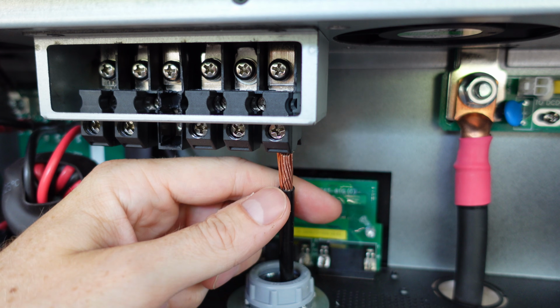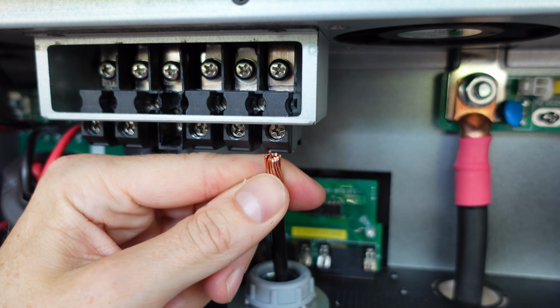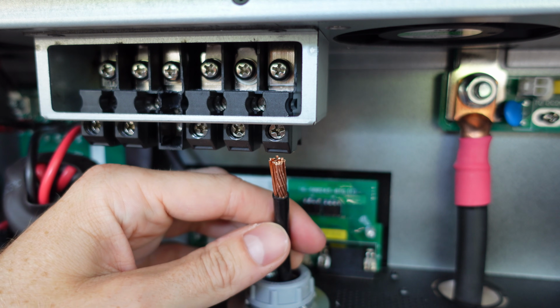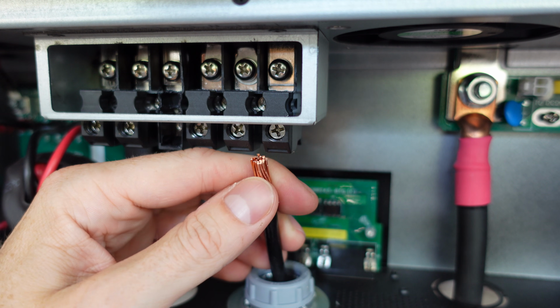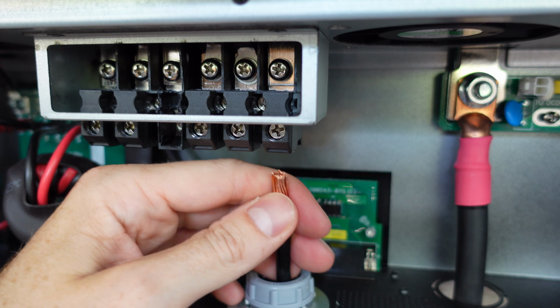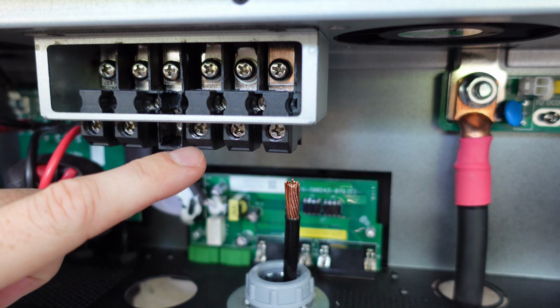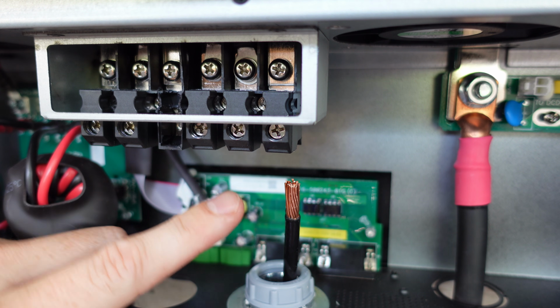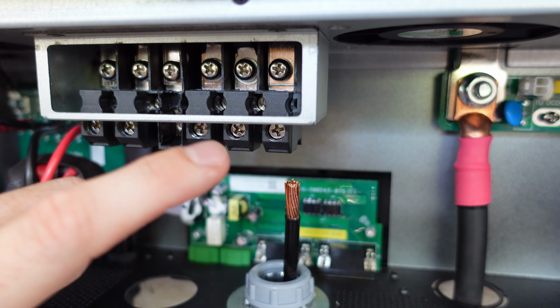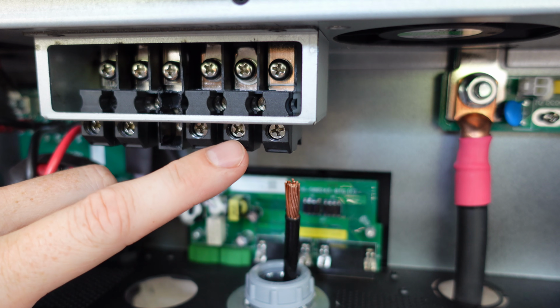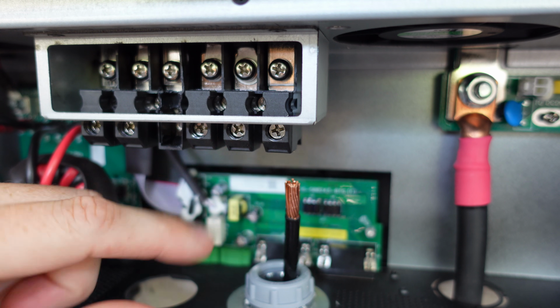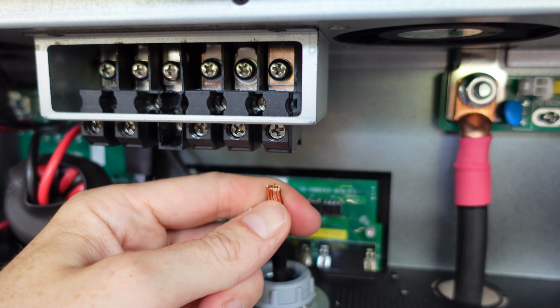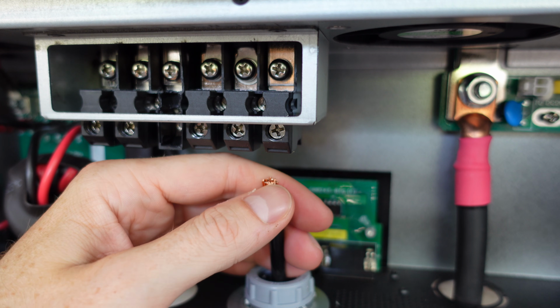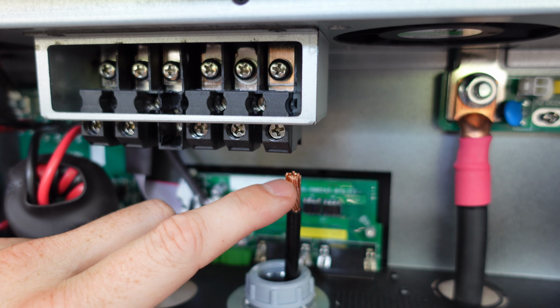Now with this wire here, you see it's not round anymore. I've sort of squeezed out the strands a little bit, and my goal is to try to flatten it just a little bit, make it a little bit rectangular shape. These terminals are actually not very good on these inverters. So if you put a round wire in there and then you tighten this down, the clamp that tightens down is going to apply force in only one location of this wire if it's round, whereas if you've got it a little bit flat, it's spreading that force over a greater area.